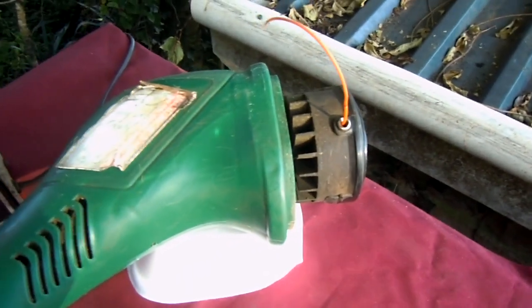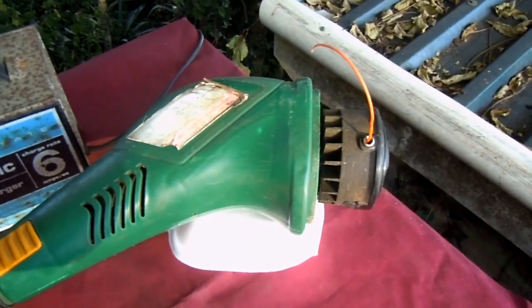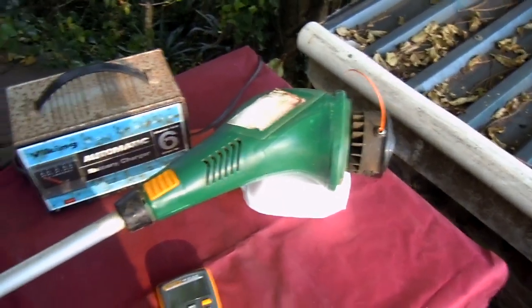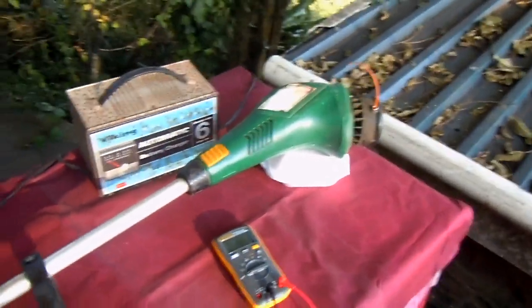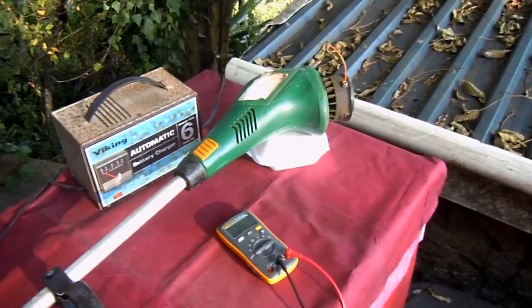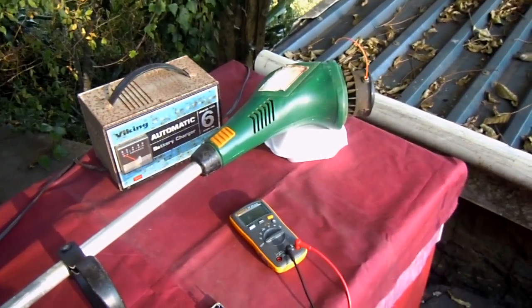By doing that I could identify that the problem is not actually the motor. Before I did that I looked at the motor windings. There was no reason to believe the motor was burnt out because the color of the copper windings were very nice.